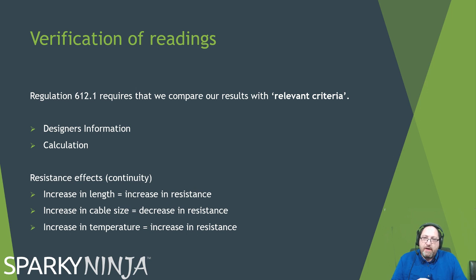I also need to be aware of other effects on resistance, like increasing length. So if I have a reading that is higher than the designer has said, it might be that the cable's length has increased. Maybe it was run in a different way. Or it might be that the cable that was selected was smaller than the designer specified. So an increase in length will increase resistance, an increase in temperature will increase resistance, but an increase in size will decrease resistance. So a decrease in size will increase resistance. Think about that for a minute.